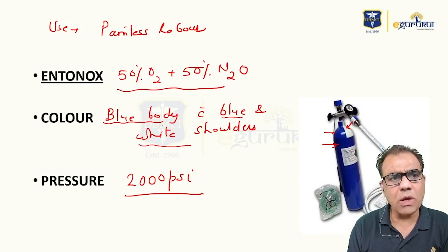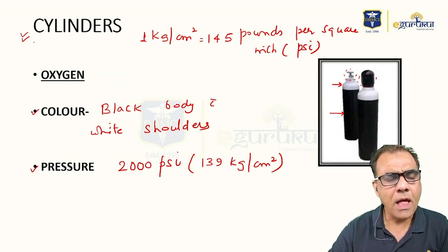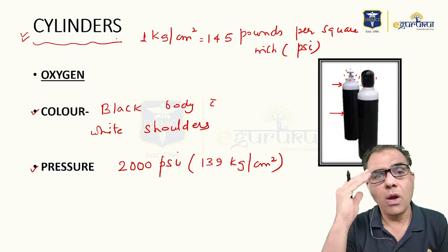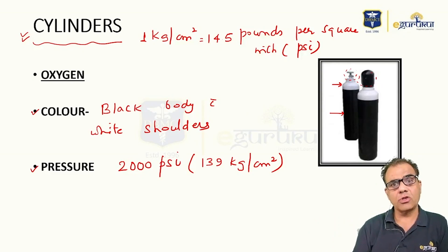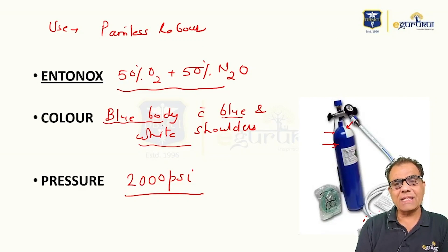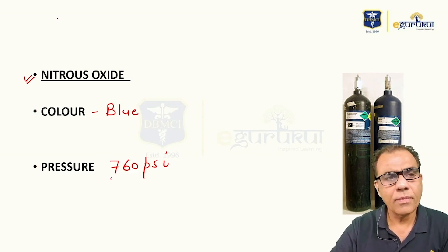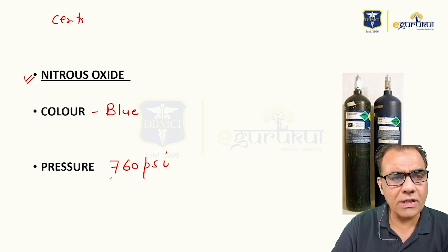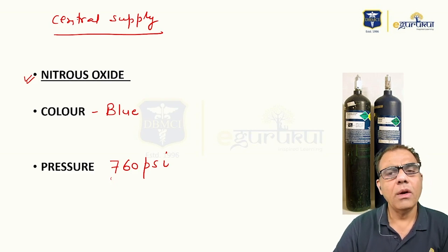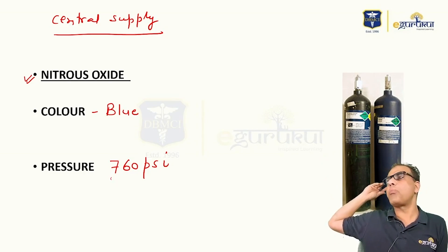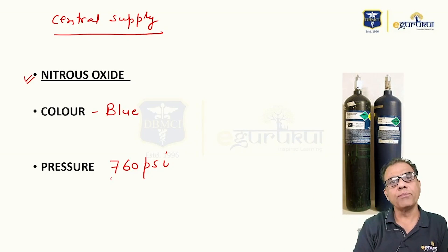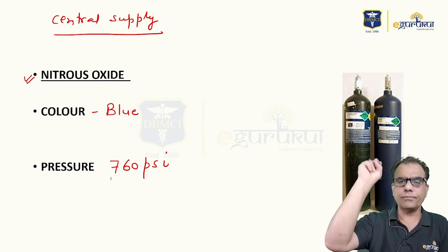Cylinders are one source, but in larger hospitals where gas consumption is more and it is not possible to change cylinders every time, gases are supplied through central supply. There is a central supply room with big cylinders, and through pipes these gases are delivered to the operation theater.